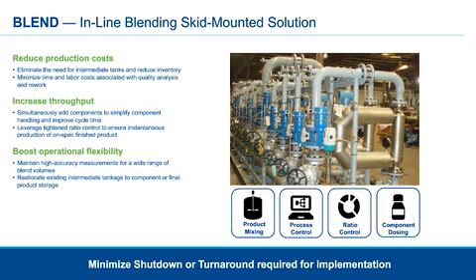They're also multivariable and now have increased tolerance to two-phase flow, which is important for such fluids as butane and gasoline blending. They also feature an important diagnostic tool called Smart Meter Verification that allows the user to simply and easily verify the accuracy of the meter. So there is no guesswork. You know that the meters are giving you the performance you need. Coriolis meters can now accommodate very large flow rates, but we still encounter cases where ultrasonic meters are a better choice, especially in crude oil blending. The choice in flow metering will be optimized based on the customer needs.